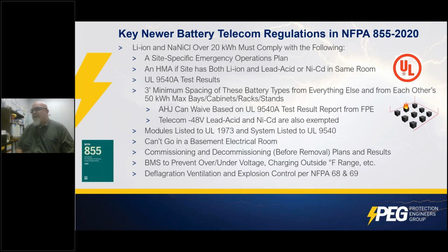You can't put them in a basement electrical room like was traditionally done with lead acid batteries. So you could do it with lead acid, but you can't do it with lithium ion. The idea is that the firefighters need to have easy access to fight the fire. You also couldn't put them on roofs over 75 feet for the same reason. You had to have commissioning and decommissioning plans and results. And they have to have a battery management system.